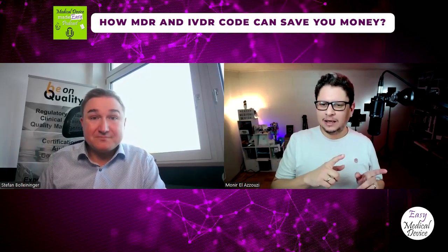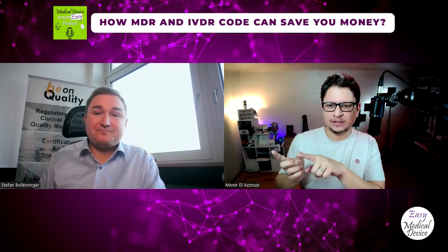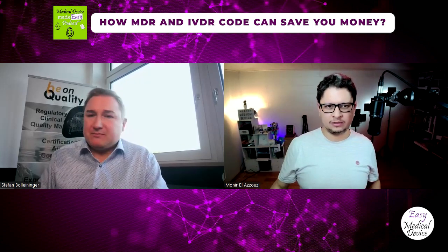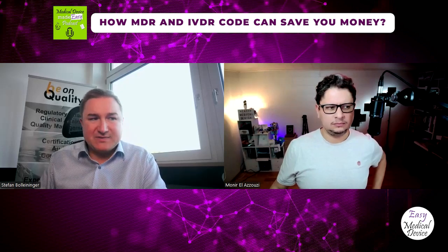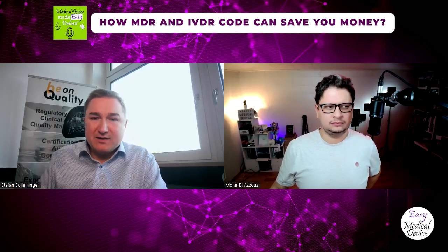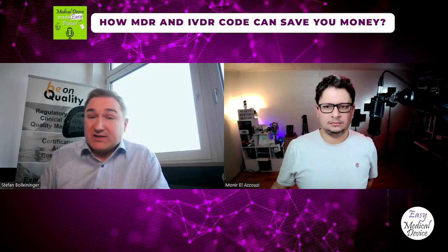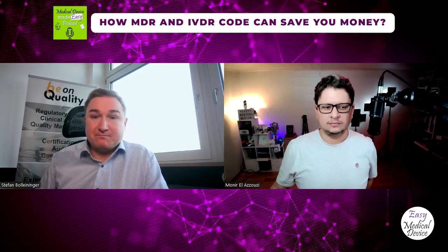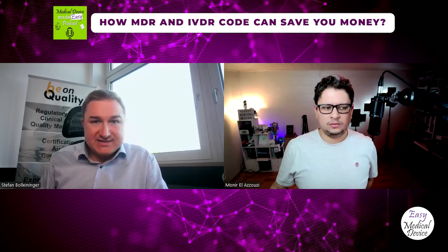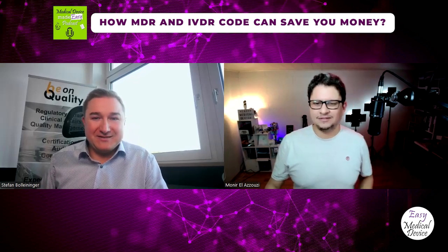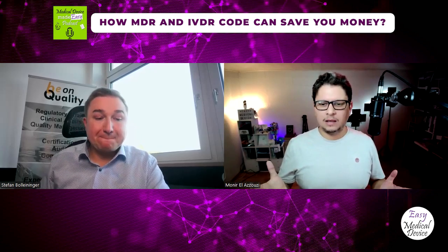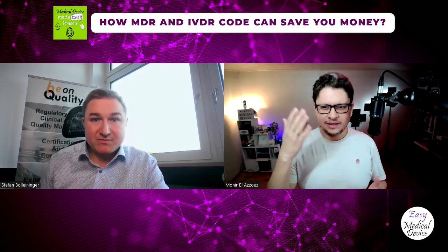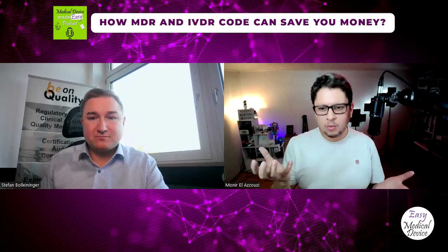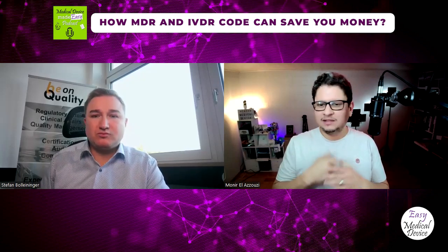So we talk here about MDR, but we also have IVDR for in vitro diagnostics. So is it the same principle, the same thing, or not? Yes, it's no big difference. The codes have slightly different namings because in vitro is a bit different from the MDA and the MDN. However, same principle, same systematic, just a different guidance with different numberings. In that case, pretty cool, and that's nice that IVDR and MDR are aligned quite well here. Yeah, exactly. So in that case, I have my product, I look at these tables, I find the right IVD code or MDR code. I give that to my notified body.